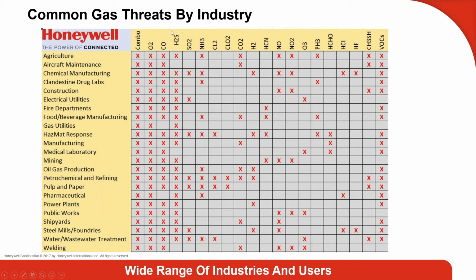Notice those sparsely populated gases are good opportunities for a single gas monitor or that fifth gas in a five-gas unit. But the most popular fifth sensor, aside from the standard four, is a PID that detects volatile organic compounds in a broad catch-all range, where it can detect a lot of methyl ethyl whatever's out there. It's not going to speciate, not going to know exactly what's there, but it gives you a higher level of protection. The wastewater treatment industry likes that extra level of protection.